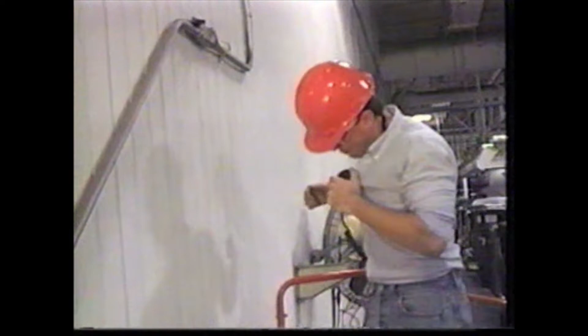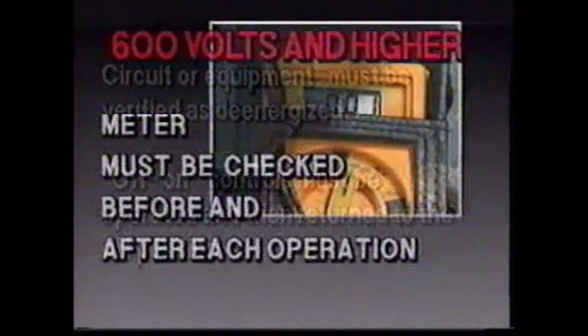Before any circuit or piece of equipment can be considered de-energized, a qualified person must meter the circuit and then operate the controls to make sure all energy is isolated, then return these controls to the off position. If the circuit under consideration is over 600 volts, the test equipment must be verified and checked before and after each use. If you're ever unsure about the correct work practices or lockout procedures you should follow, ask your supervisor or consult the company's electrical safety-related work practices.